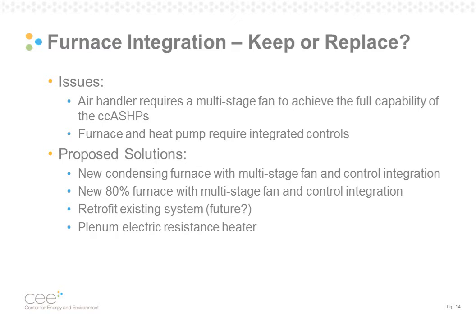The fourth option would be to install a plenum heater that could meet the full heat load of the home when the air source heat pump could no longer meet the heat load of the home. But this would mean a large plenum heater, and it would essentially eliminate the need for the furnace, which didn't fit the requirements of our study. So we chose solutions 1 and 2.